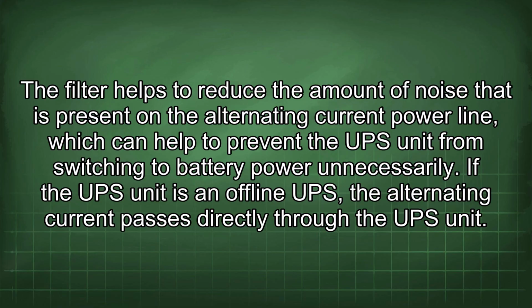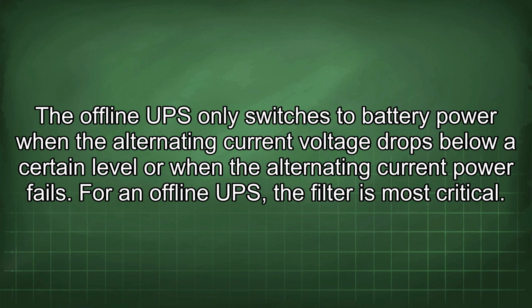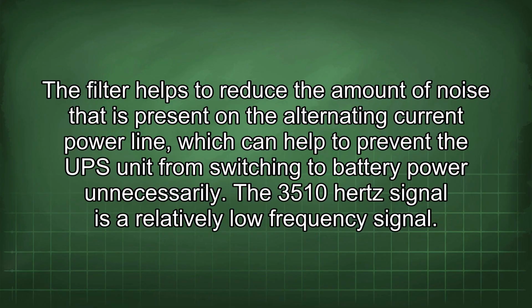If the UPS unit is an offline UPS, the alternating current passes directly through the UPS unit. The offline UPS only switches to battery power when the alternating current voltage drops below a certain level or when the alternating current power fails. For an offline UPS, the filter is most critical. The filter helps to reduce the amount of noise that is present on the alternating current power line, which can help to prevent the UPS unit from switching to battery power unnecessarily.